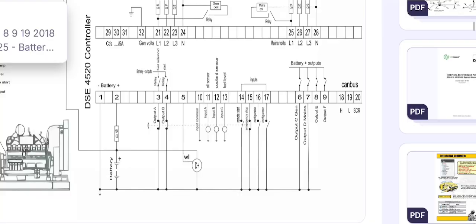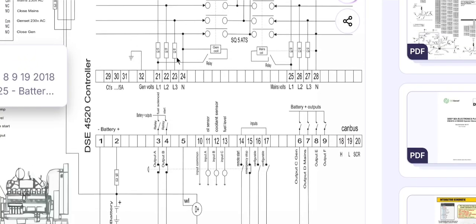As you can see here, this is the complete typical wiring diagram of this controller. Pin 1 is battery negative input and 2 is battery positive input. And here, as you can see, the fuel solenoid relay output is pin number 3, and 4 is for the start, that means for the cranking. Pin 5 is the battery charger sensing input from the engine alternator. And here we have inputs common. This is the common, meaning the ground wire you should insert here.